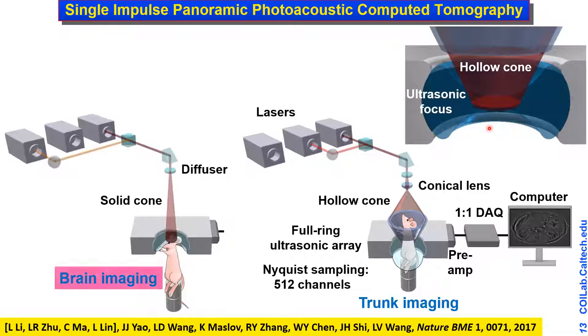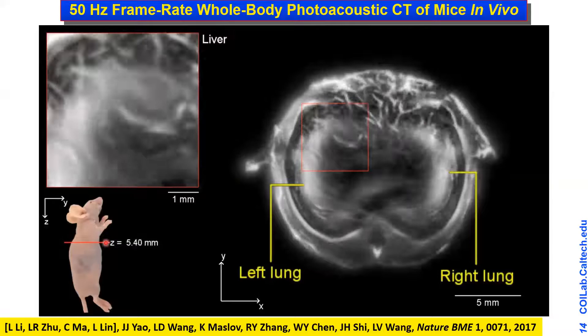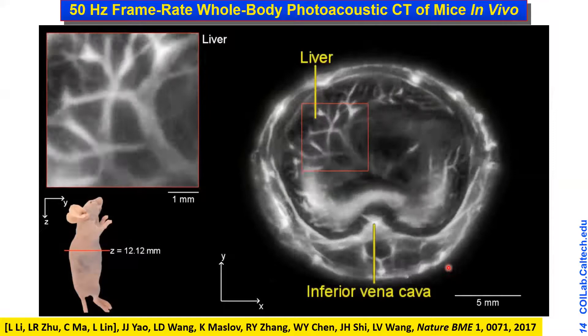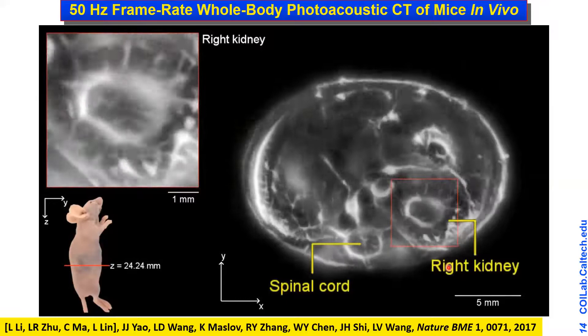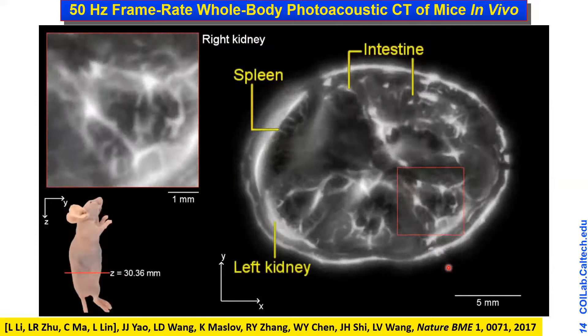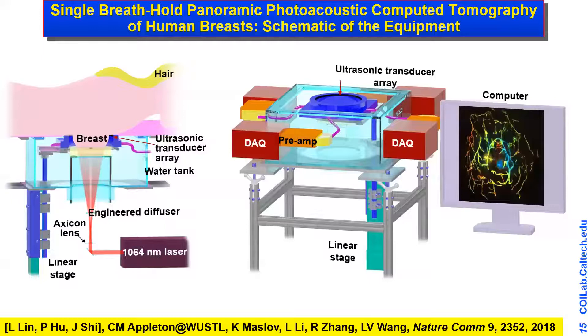The system can be easily reconfigured for brain imaging using a diffuser for solid-beam illumination. The hollow cone beam uses elevational focus so the elevational direction does not need reconstruction, while in-plane resolution comes from the inverse Radon transform. In a demo scanning along the trunk, you can identify different organ structures without any injection of contrast agents — very useful for drug discovery, where pharmaceutical companies want to monitor the same animal over multiple months without worrying about radiation dose from x-ray.